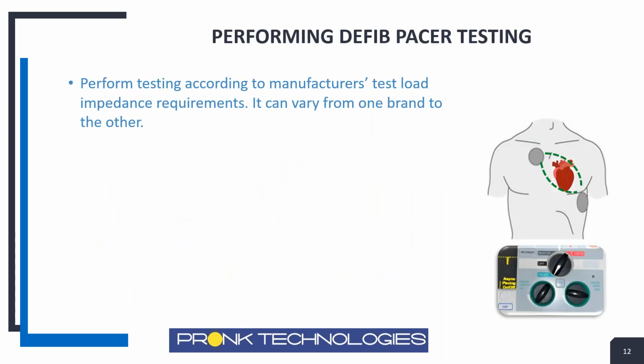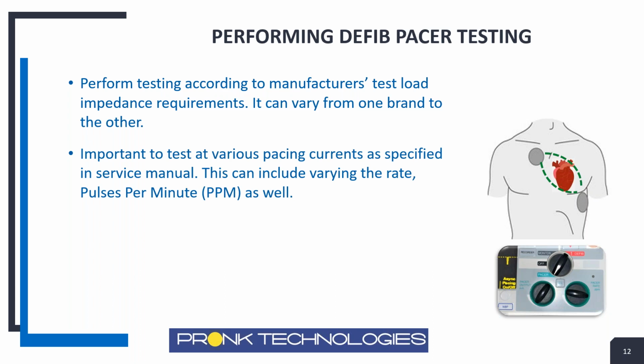So performing pacer testing, we want to make sure we're doing it according to the manufacturer's requirements. They also have test load impedance requirements for pacer testing. It may not always be the same impedance, so always be sure to check the service manual to see what impedance the manufacturer wants me to test the pacing for that particular device. So make sure you check that. Always important to do at the various pacer currents specified in the service manual, or you may want to consider that as a best practice, even if it doesn't specify that, just to make sure it works across a wide range, including the pulses per minute as well.